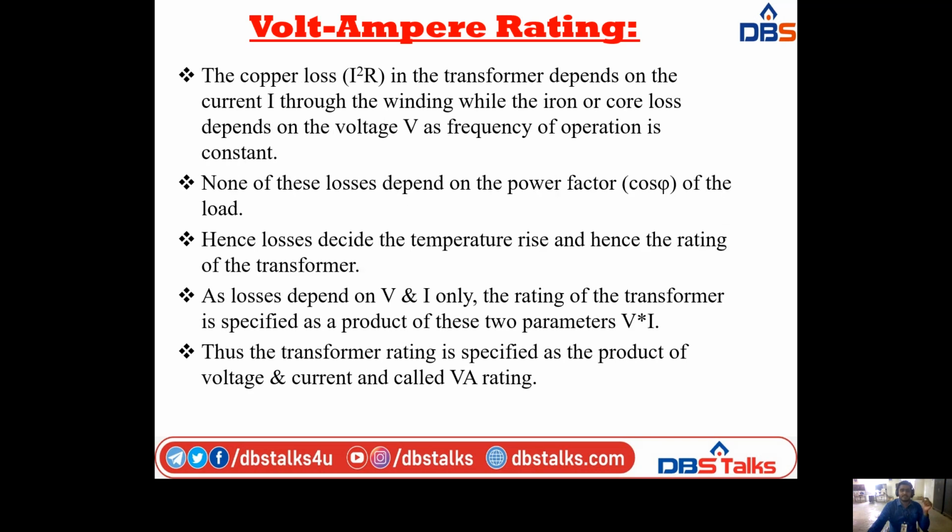Next, the copper loss in the transformer depends on the current through the winding, while the iron or core loss depends on the voltage V, as the frequency of operation is constant. None of these losses depends on the power factor, because it is an alternating quantity. That's why the losses do not depend upon the power factor of the load. Hence, losses decide the temperature rise, and hence the rating of the transformer.